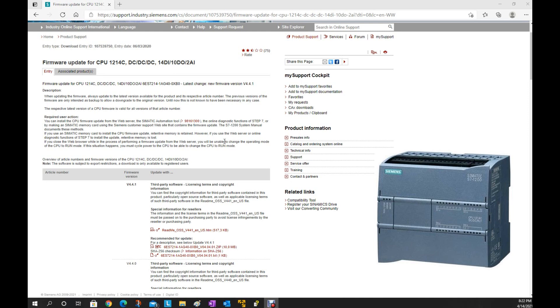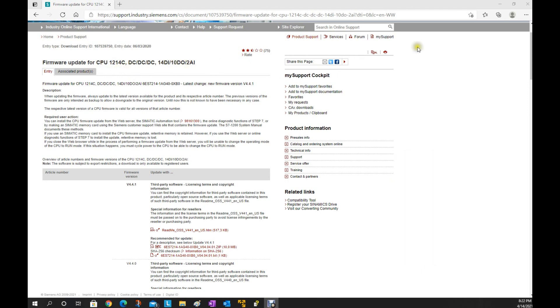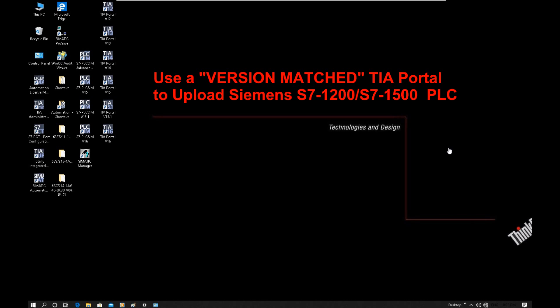In this video the CPU I am using is a 1214 DC/DC/DC. Basically all the Siemens S7-1200 PLC series have a similar idea. To upload the program from a 1200 CPU, one important principle: we have to use the same TIA Portal version that was used when we originally programmed this CPU.